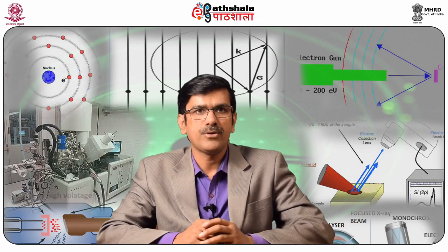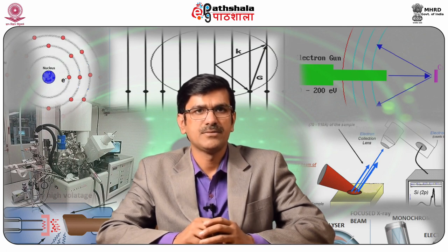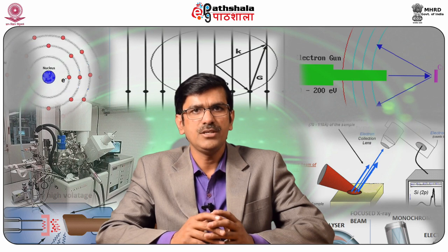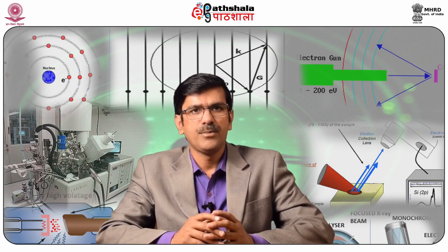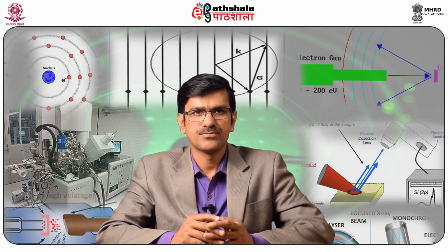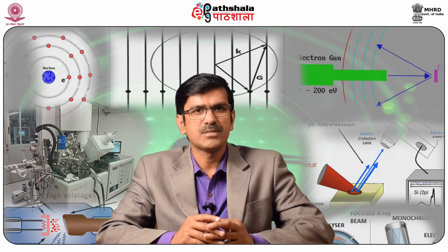XPS requirements from the hemispherical energy analyzer: lower pass energy (E0) usually gives better resolution in XPS. However, improper values of pass energy and input/output slits result in spectrum shape distortion. It is advised to make test XPS recordings for a well-known material and verify the obtained spectral parameters with published data.